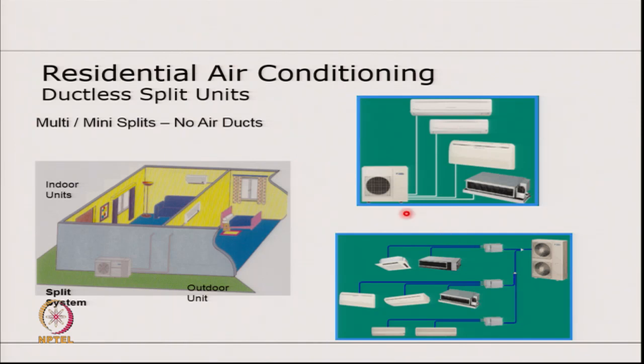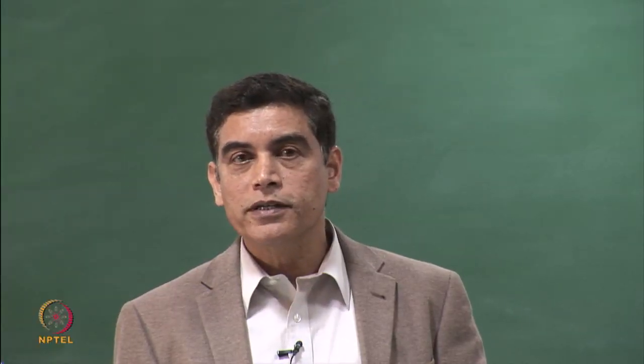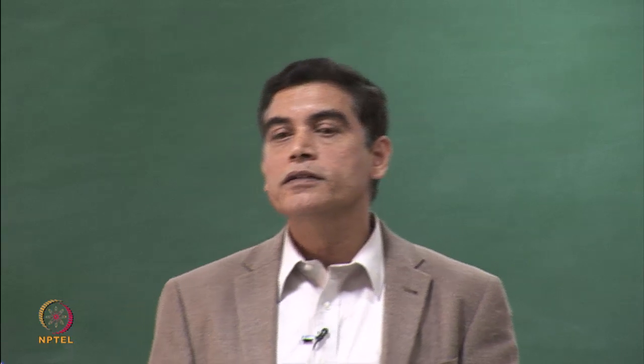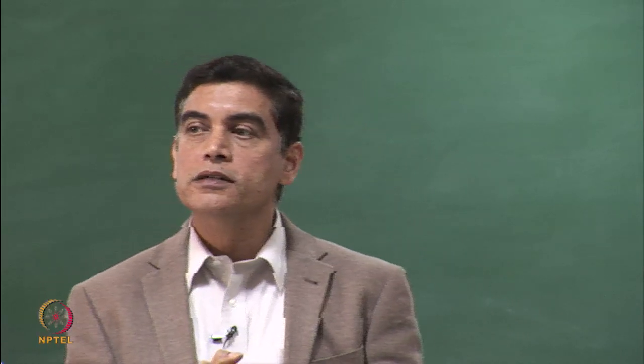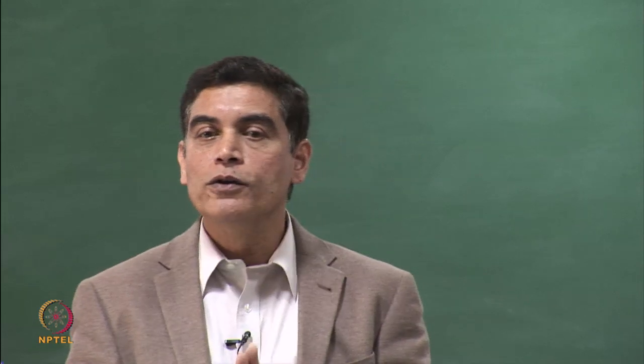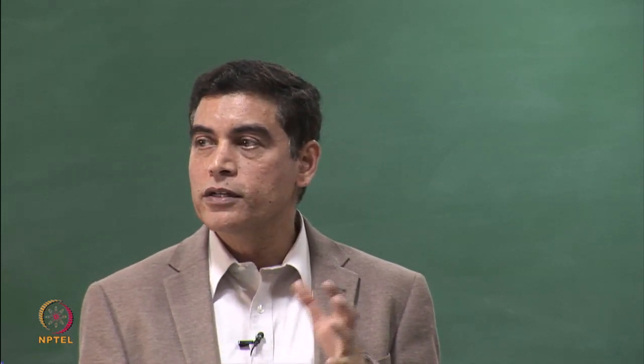Now when we are looking at ductless split units, we could look at conventional systems which are fixed speed systems also connected to multiple indoors, and this is one example of that. Now inside this unit there could be a compressor which is either modulated digitally, which means the compressor continues to rotate but the compression is switched on and off. When we looked at compressors, we looked at two different ways of variable speed. One was true variable speed where the compressor motor changes speed, another was we modulate the duration for which the compressor is in compression and then it is offloaded, so it's unloaded and the scrolls just continue to rotate without doing any compression.